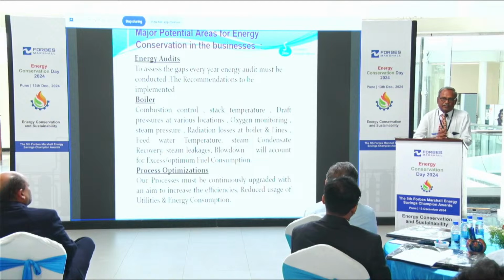There we converted from overhead firing to underhead firing, and installed combustion control by taking the steam pressure into consideration, thereby controlling the fuel feeding also. Now, for the last 2 years, the consistency of steam availability to the plant is very good, and unburns are reduced to about 6%. So these small things can make a good impact.